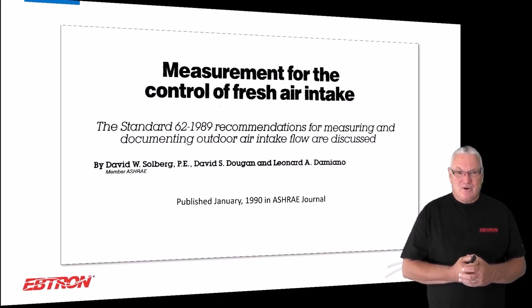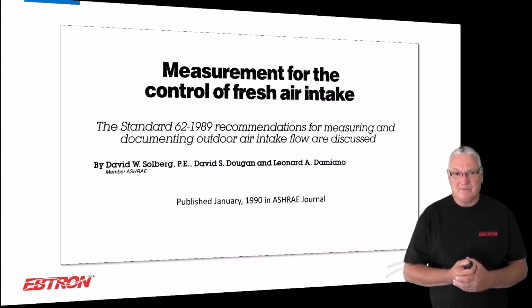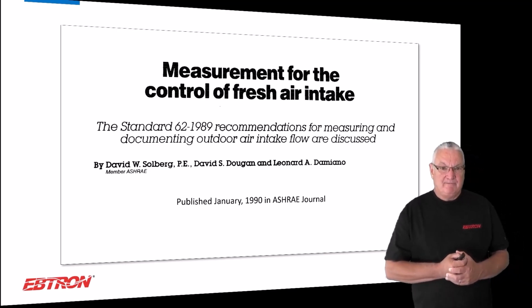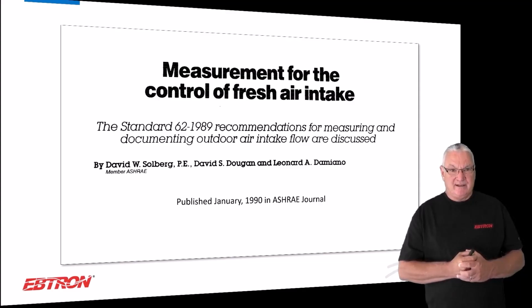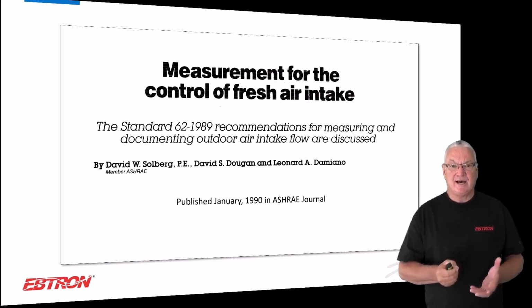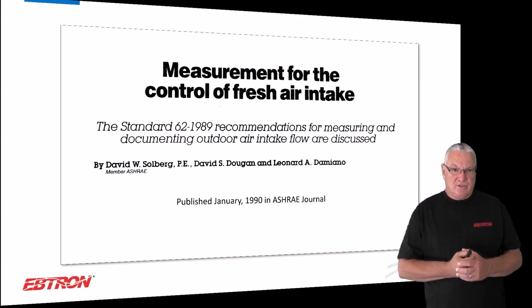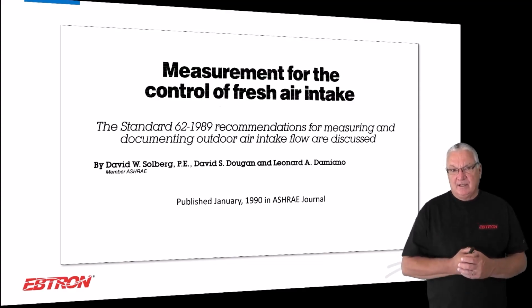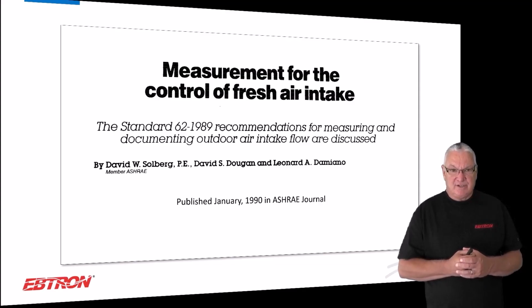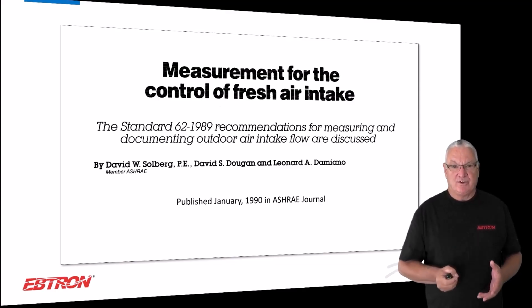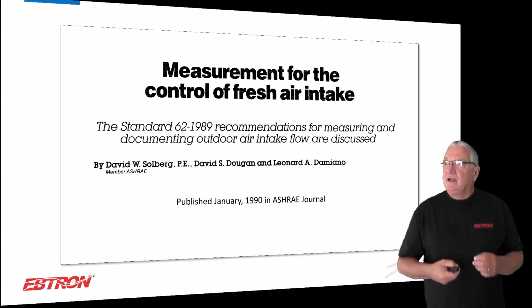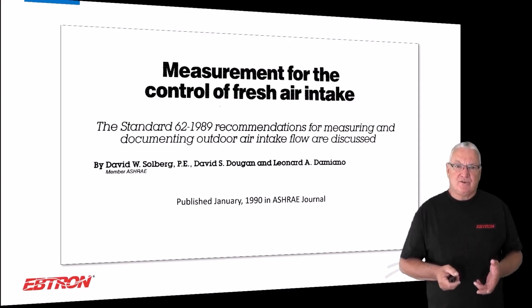Okay, and so back in the 70s and 80s, we had indoor air quality problems that resulted from the energy crisis of the 70s, and ventilation rates were reduced. And ASHRAE decided to do something about it and significantly change Standard 62 in 1989 to bring the ventilation rates up. And so seeing what was going to happen there, we wanted to get ourselves in a position where people realized that they couldn't do what they were doing, which was just set it and forget it, and they needed to measure and control outdoor airflow rates.